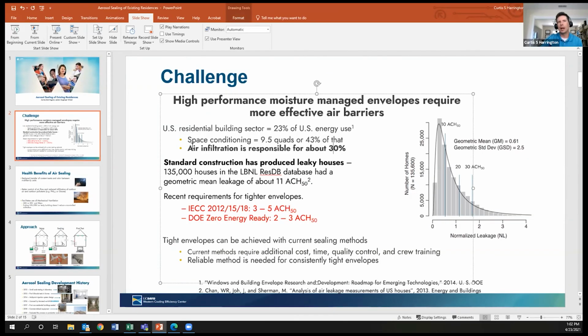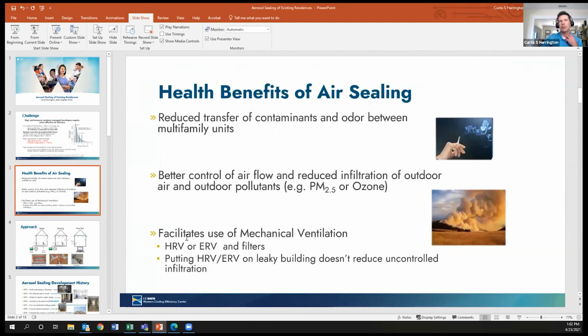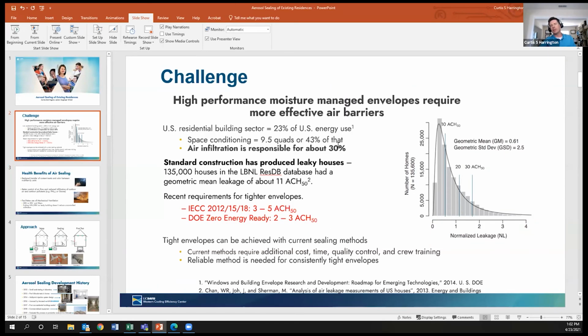Yes, I should caveat this statement. This includes ventilation for the building, but yes, 30% of the load in the building is due to outdoor air coming in. Sometimes it's brought in on purpose through ventilation systems, but otherwise it's through uncontrolled infiltration. If you were to put in an HRV or ERV, this number would go down significantly because you'd be exchanging that heat when ventilating your building. But infiltration still happens regardless—if you don't have a tight building, you're going to have uncontrolled infiltration. This includes both that and ventilation-related loads.